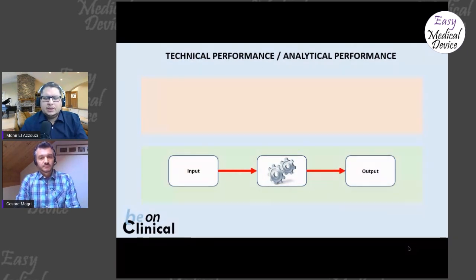Okay. Here we also have the development of software. There is this kind of V-shape for the development of software. Any software should go through that. So here we are really talking about the verification and validation process for software from beginning to end, to prove that our software is really designed to do what we ask it to do. You would not refer to the low-level tests, like the module tests. That's not what's going to be interesting. But if you do some sort of system test with your software, you probably have the reports there that you can also use in the clinical evaluation, so you can reference them.